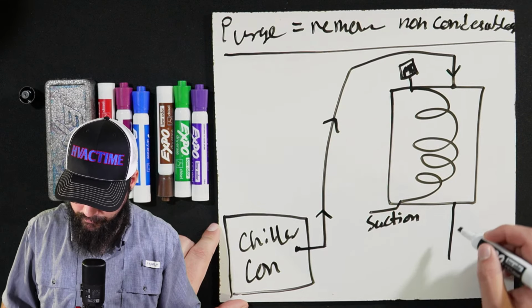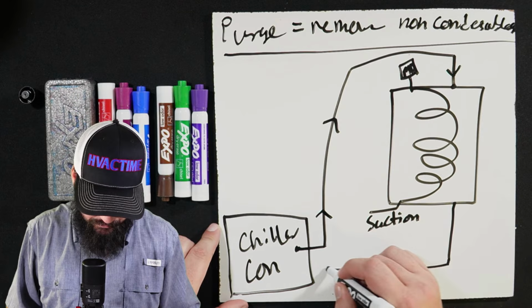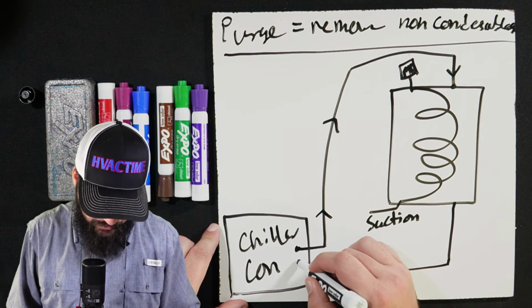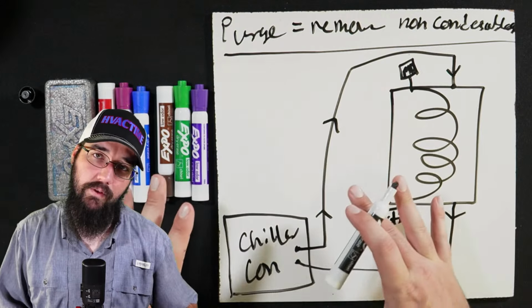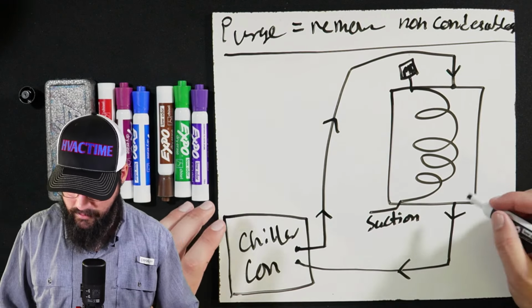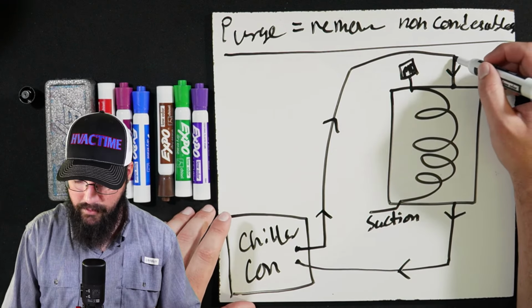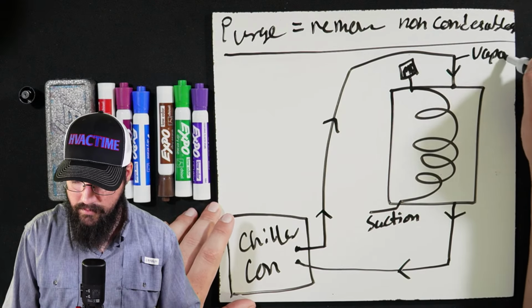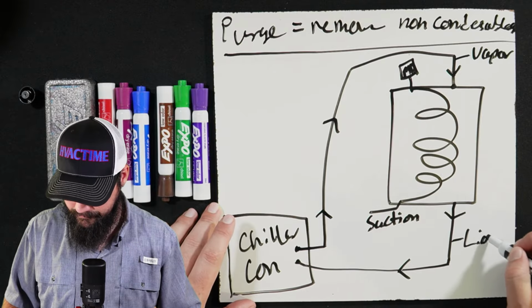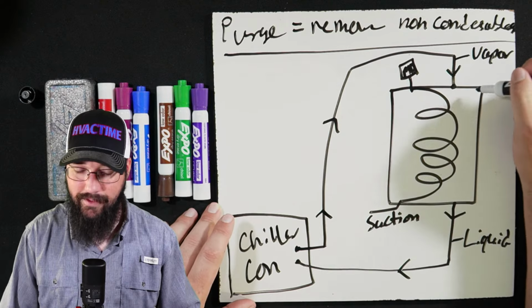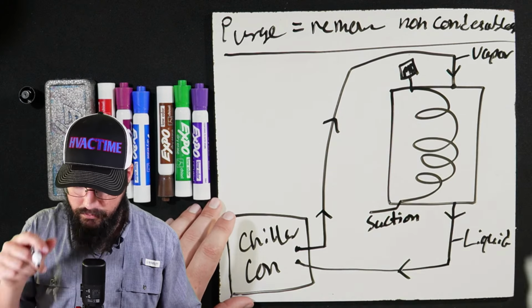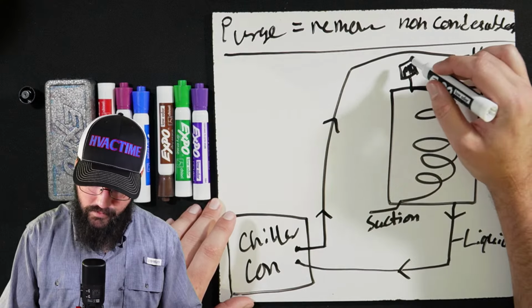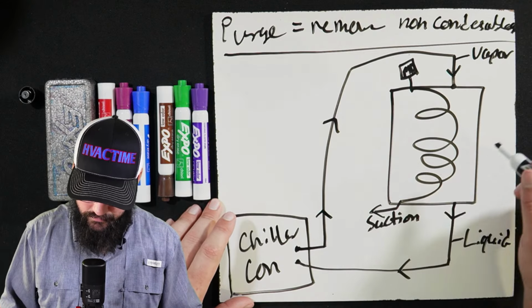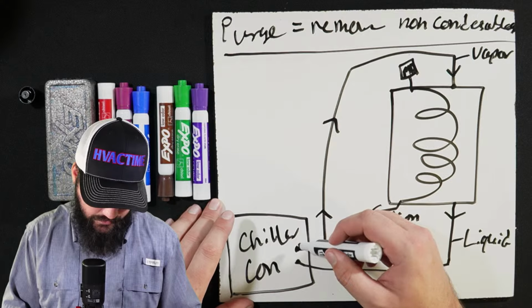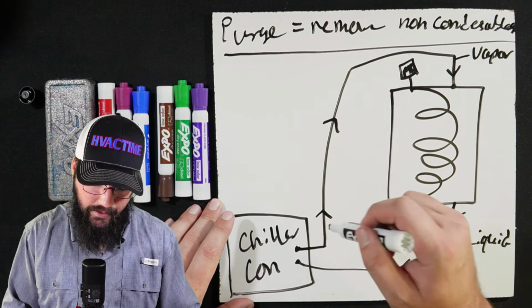Okay, so then we leave the bottom of the purge evaporator and come back to our condenser at that midpoint. So we're trying to reintroduce everything basically where it came out of. But it's coming in here as a vapor, and it's leaving as a liquid. It's part of the condensing process.